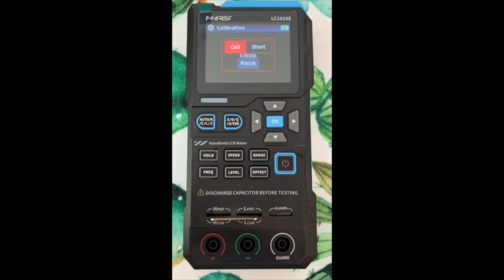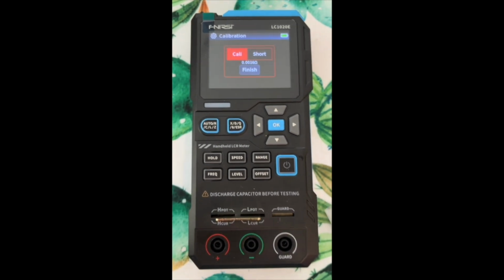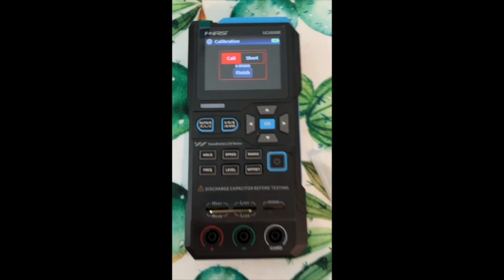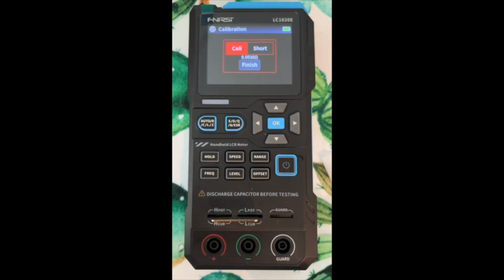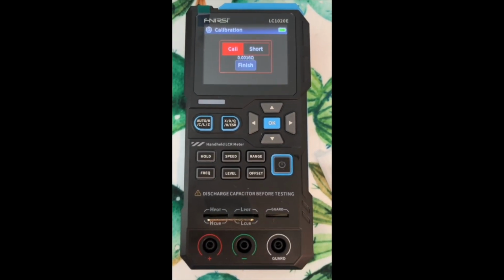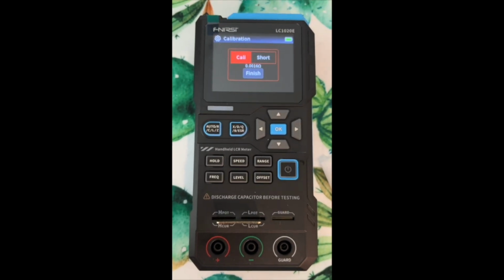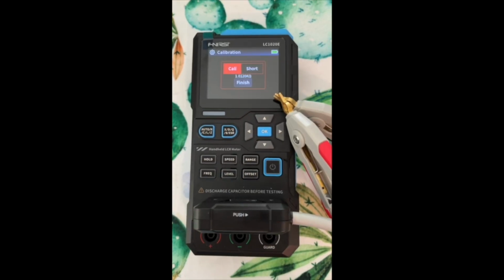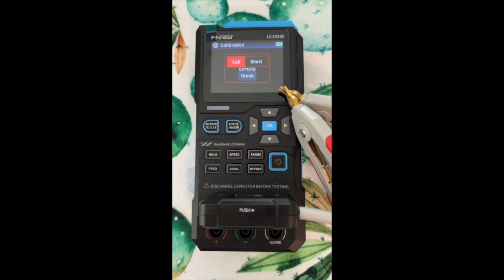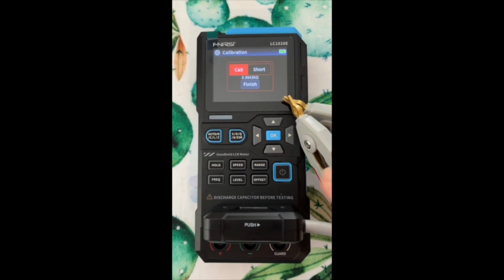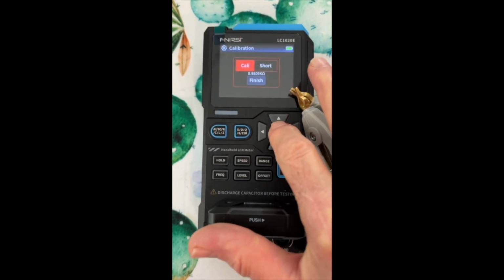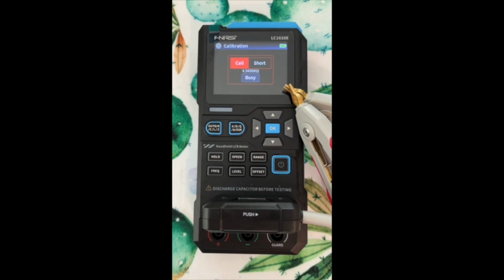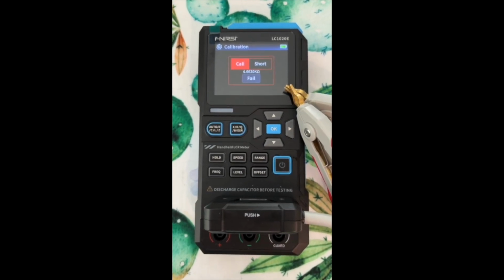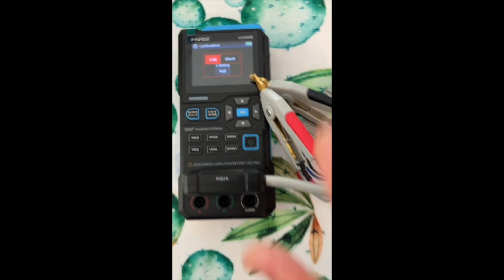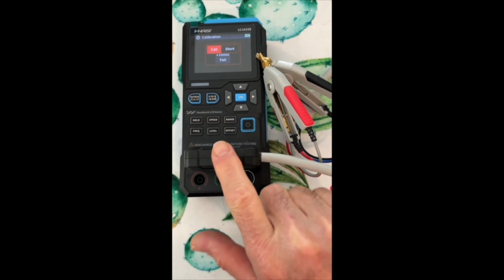Now the next test I'm going to do is with these Kelvin leads. We're going to go ahead and see if it does the same thing, but as I've tried it, it always fails. So I'm going to assume that these are bad. With the Kelvin leads inserted, we're going to try the calibration on the shorting mode, and we'll see what happens. And as you can see, it fails. So I'm assuming these leads are bad.